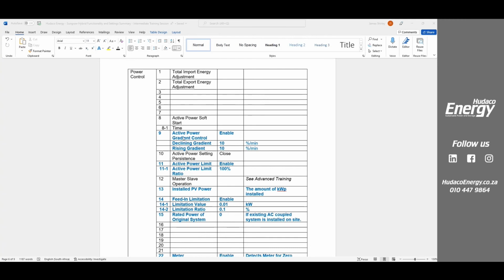Okay. Active power is not as we normally know if you're an electrician or electrical engineer, where we normally talk about active and reactive power. This active power on the Sungrow inverters really talks about the PV power coming from the solar panels. So when we start, we will enable our active power limit and we set that to 100%. In other words, if we want to feed back any active power to our loads, we're allowing 100% of our PV panels to feed back to those loads. Okay, so that's what this active power limit refers to.